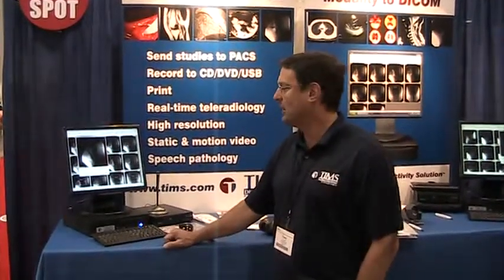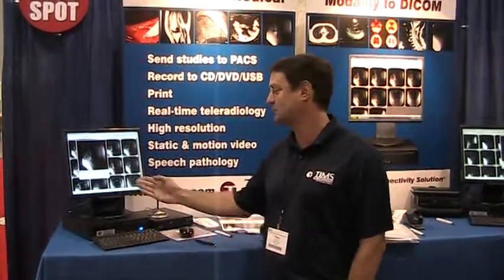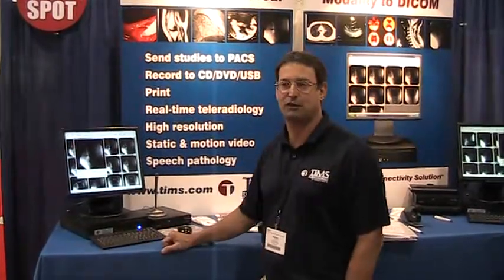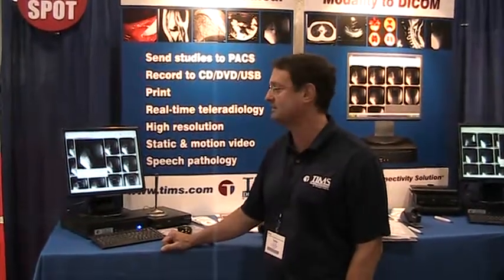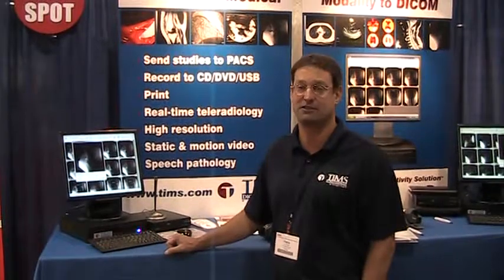But it's not just for DICOM conversion. We also can be attached to any fluoro system for long format capture for things such as speech pathology and esophagrams. And that's because those studies take a very long time — they can be a few thousand frames or several thousand frames. And if you want to be able to send those to PACS and keep up with the study in real time, you do need a capture device such as the TIMS DICOM system.